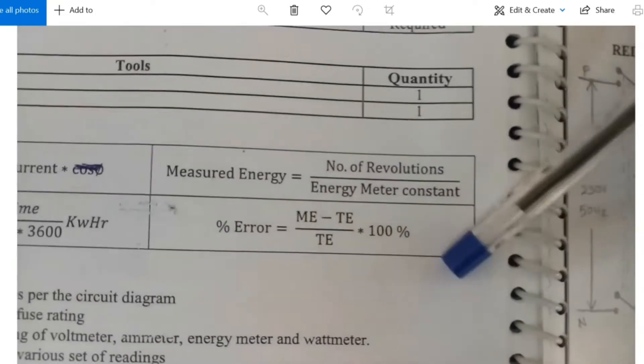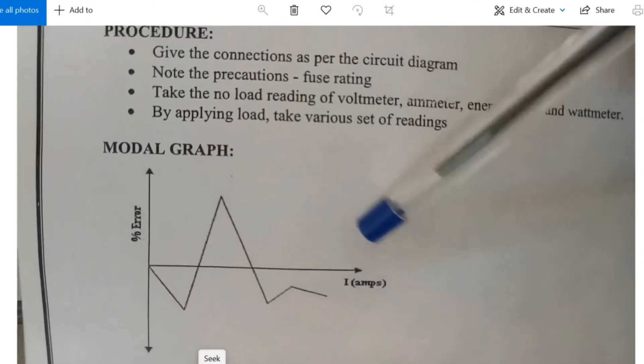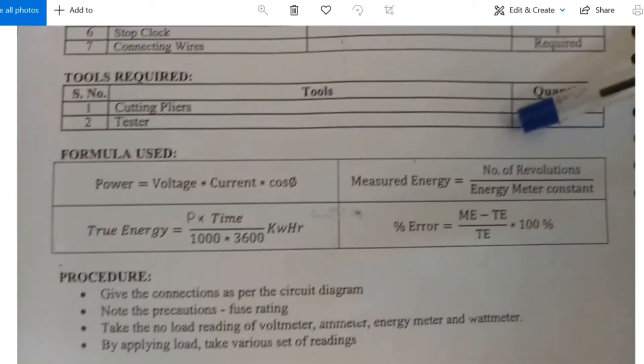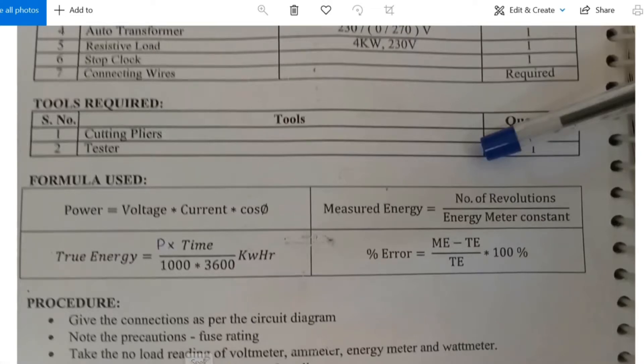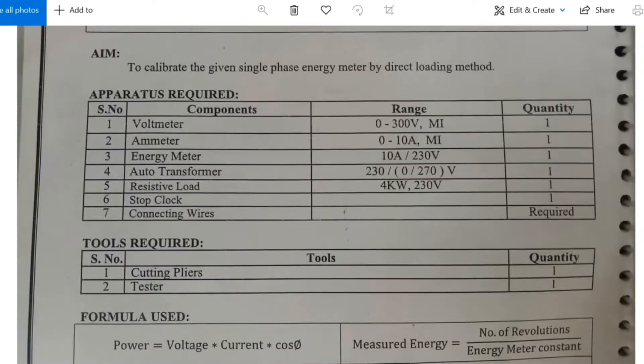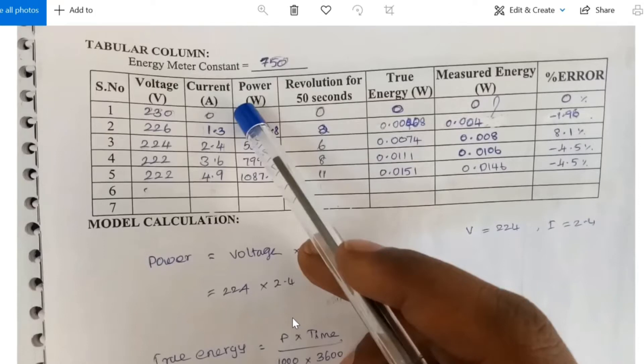Moving to the procedure: connections are made as per the circuit diagram. Note down precautions and fuse connections. Take no load values and readings should be taken for all loaded conditions. Repeat the experiment up to the maximum current of 10 amps. The tabular column includes energy meter constant 750 for 50 seconds: voltage, current, power, revolutions for 50 seconds, true energy, measured energy, and percentage error.